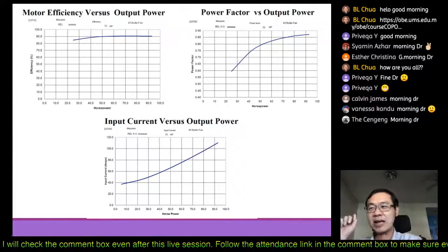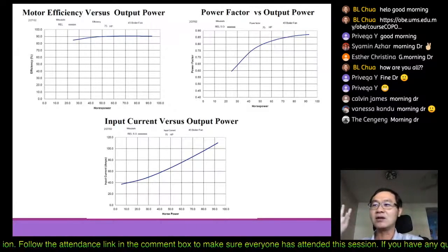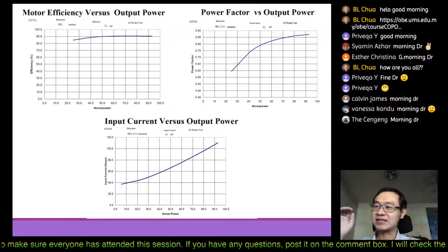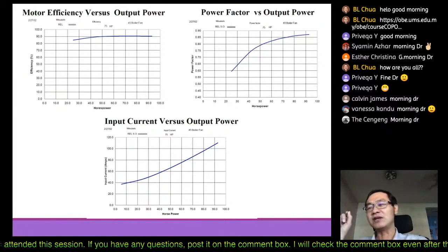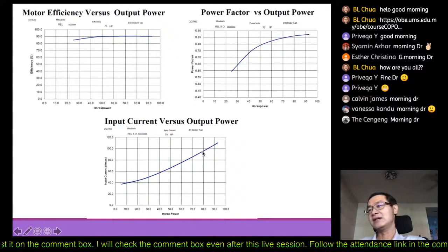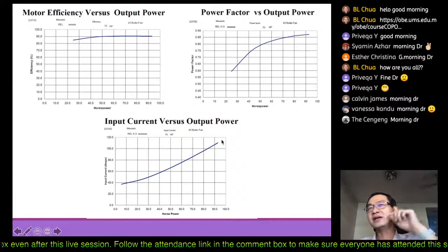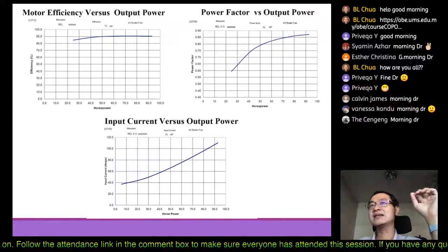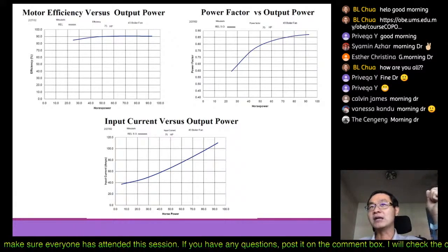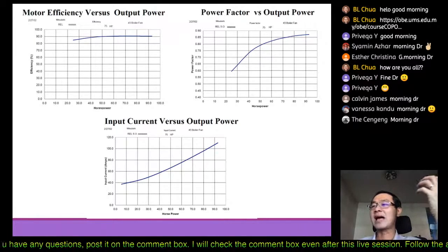So it tells you something is wrong, just like our body. When we have flu, it tells us something is wrong, because our body, or the system itself, will operate at a certain range of current. But if, with the same fan example, the current draw now increases, again there is a possibility that the fan has started to break, maybe lost, broke. Why did it break and cause the load to be higher?